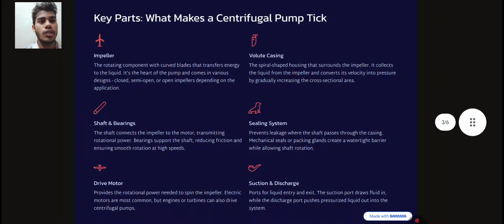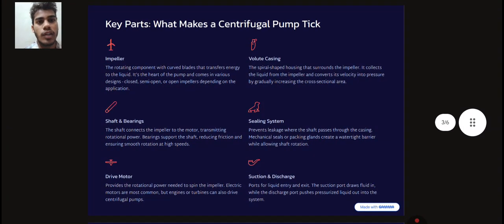Key parts: what makes a centrifugal pump tick. First one, impeller. The rotating component with curved blades that transfer energy to the liquid. It's the heart of the pump and comes in various designs: closed, semi-open, or open impeller, depending on the application. Shaft and bearings. The shaft connects the impeller to the motor, transmitting rotational power. Bearings support the shaft, reducing friction and ensuring smooth rotation at high speed.